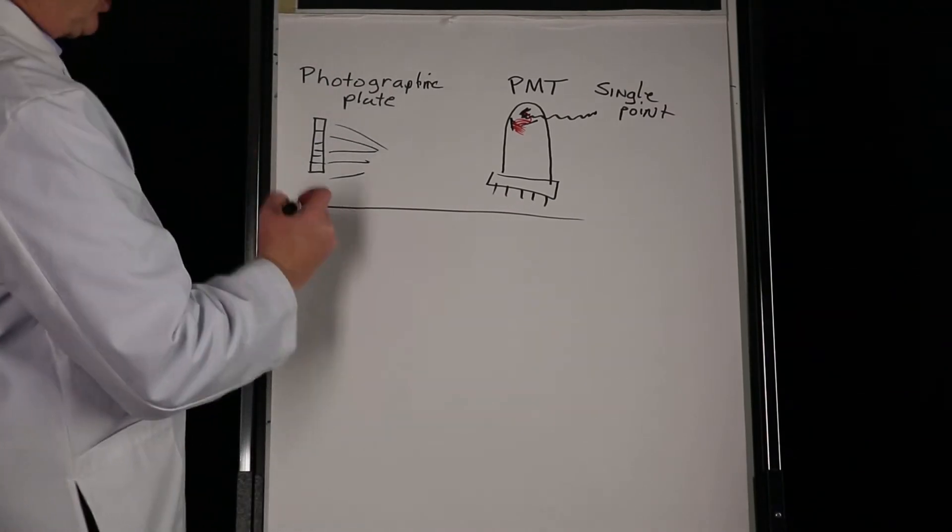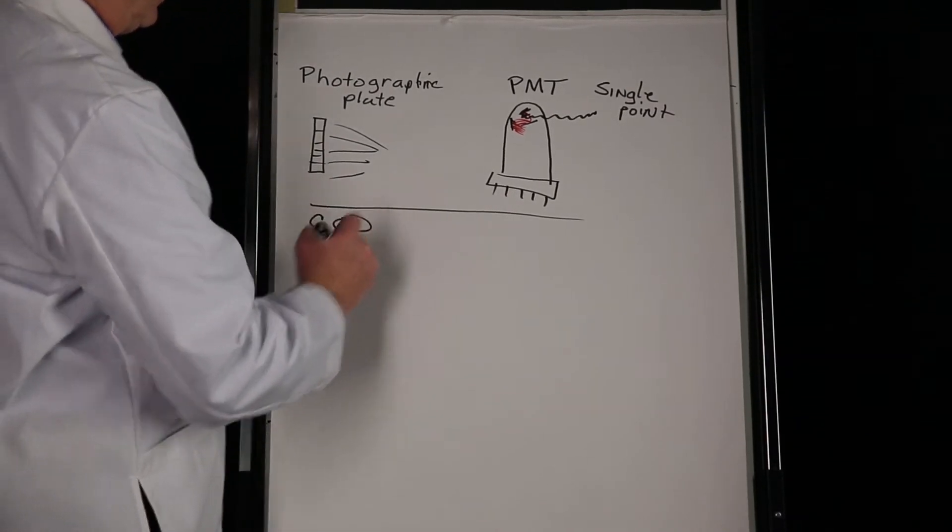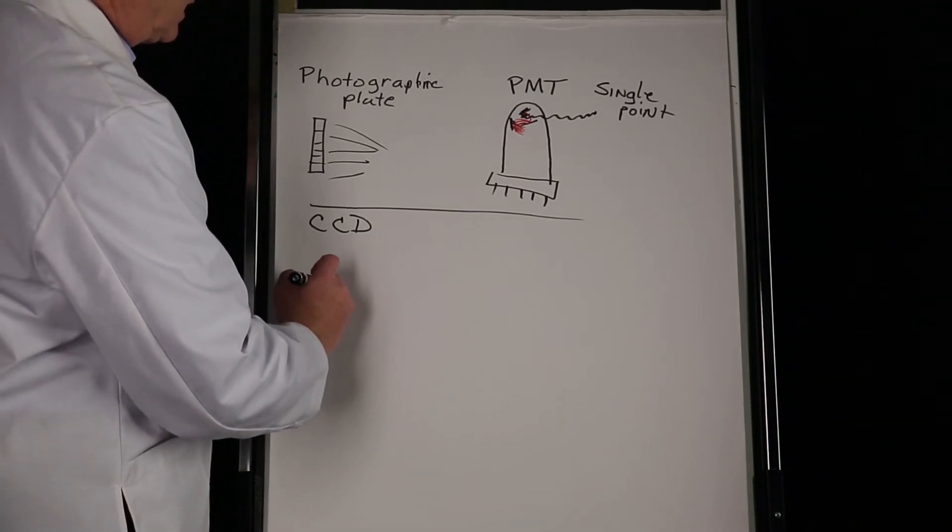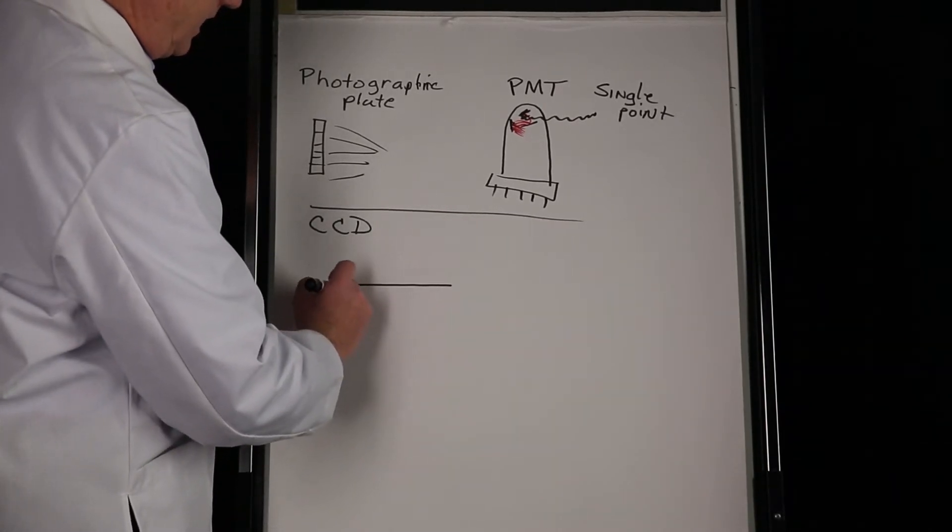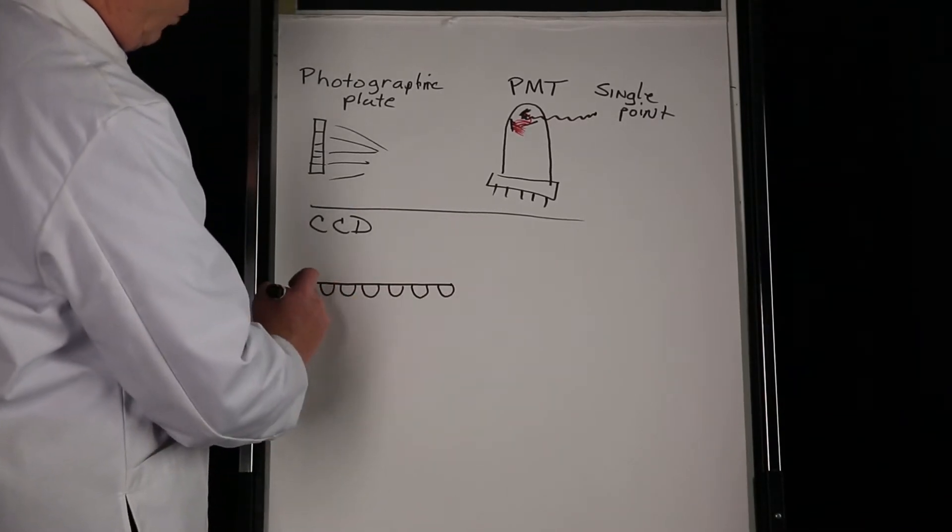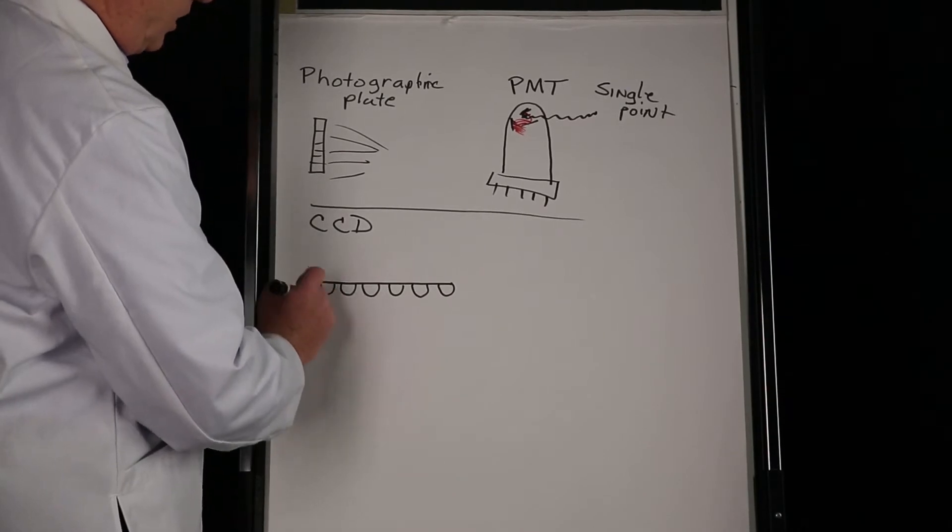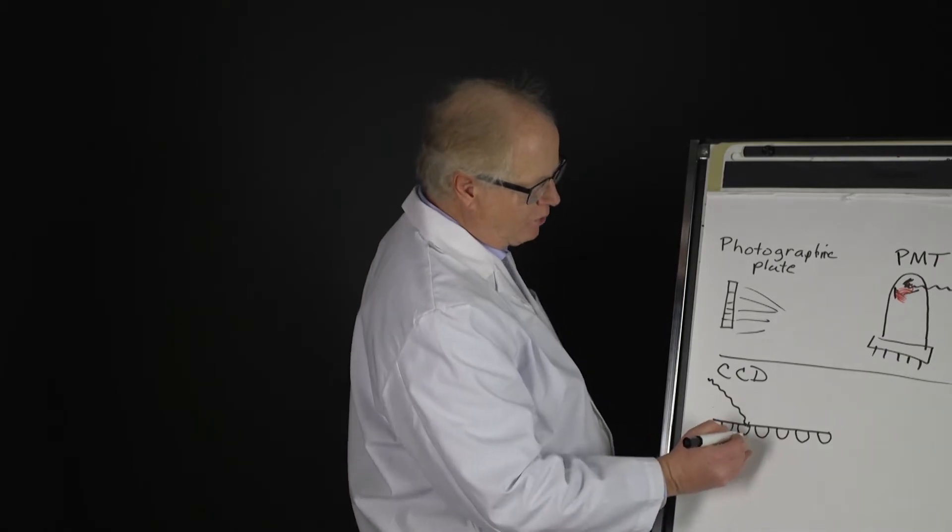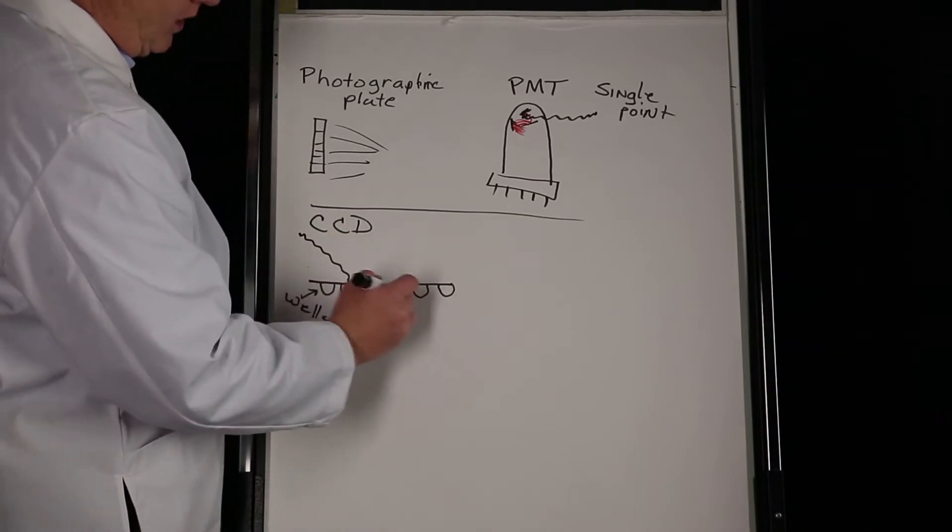All of that really changed and surged to the forefront with the charge coupled device detectors coming online. A charge coupled device detector is a solid state system consisting of a series of wells, electronic wells on the surface. We'll call them wells, and then when a photon arrives in a particular well an electron would get promoted and we would begin to fill up that well.